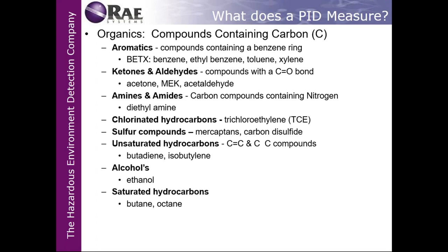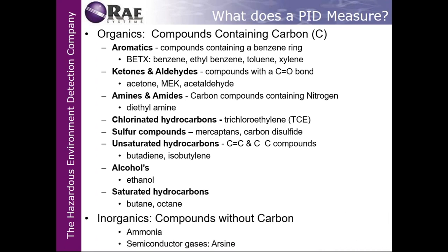Amines and amides, carbon compounds containing nitrogen, chlorinated hydrocarbons, sulfur compounds, unsaturated hydrocarbons, alcohols also, and saturated hydrocarbons like butane and octane. Take my example with gasoline: people will measure gasoline with a PID better than with just using an LEL sensor. Inorganic compounds without carbon, like ammonia and semiconductor gases like arsine, will ionize, but they have a high correction factor.